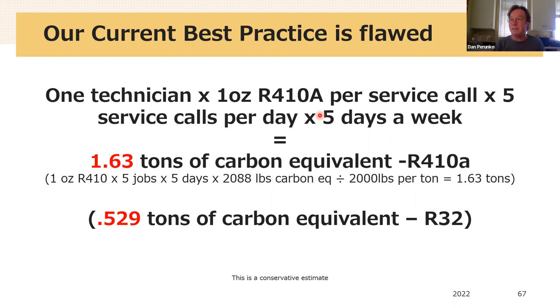This isn't even a leak. This is just a service practice. Other practices are being developed where we test air conditioning and heat pump systems without hooking up to the refrigerant charge, and that's a step we need to take when I talk about new practices. We need to rely on actually hooking up to the refrigerant loop less than we used to in the past, because it's impossible to do it without releasing refrigerant.